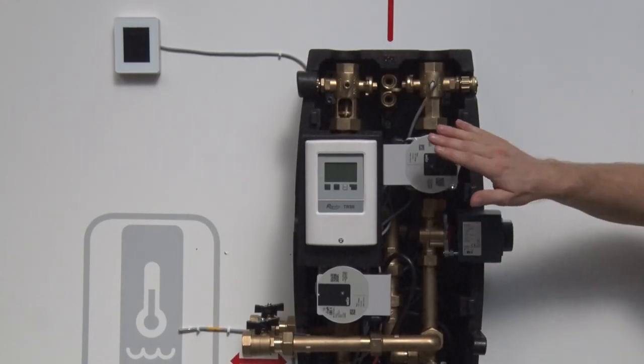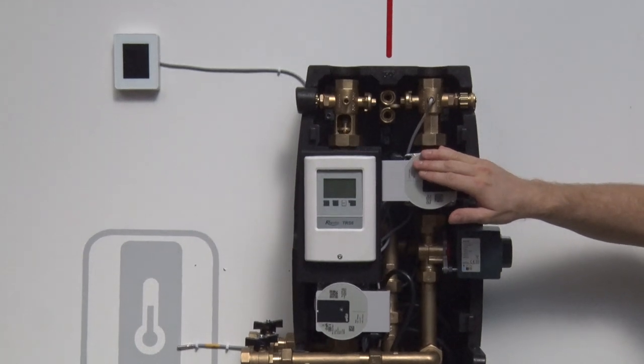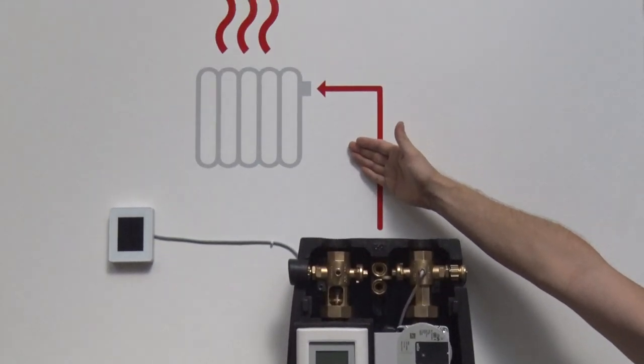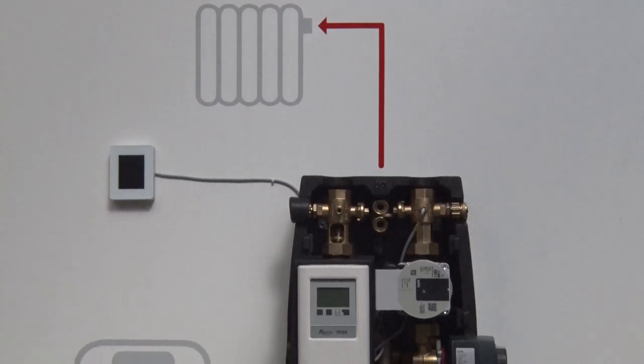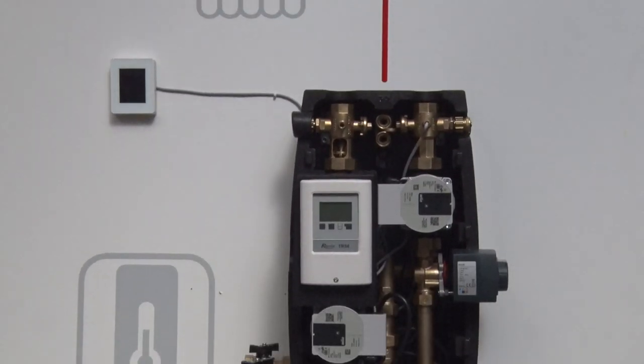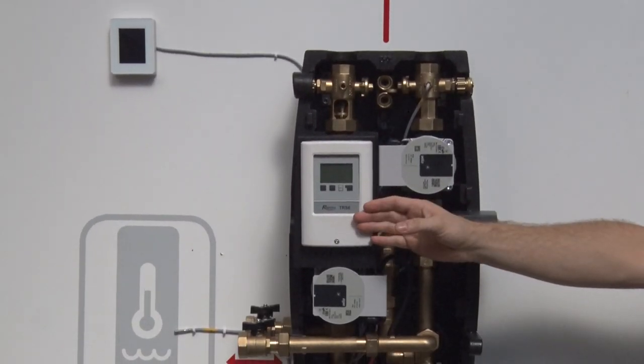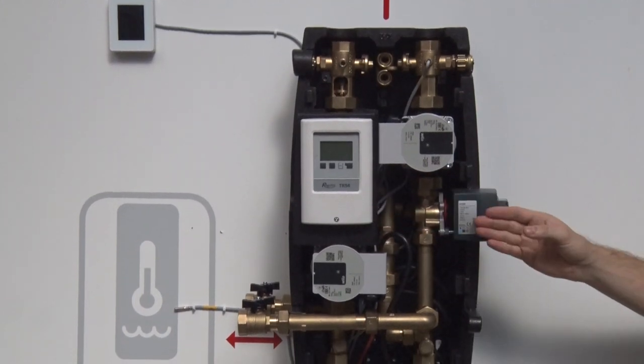The other circulation pump is intended for the heating circuit, where it mixes heating water to the weather compensating temperature set in the controller using a motorized three-way mixing valve.